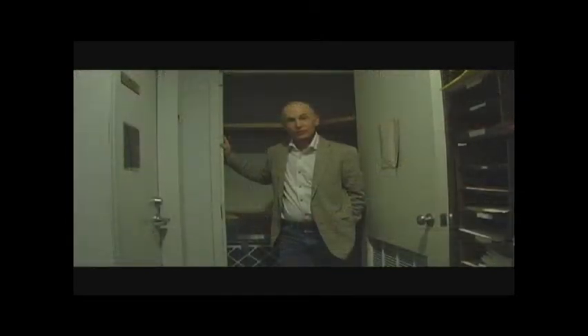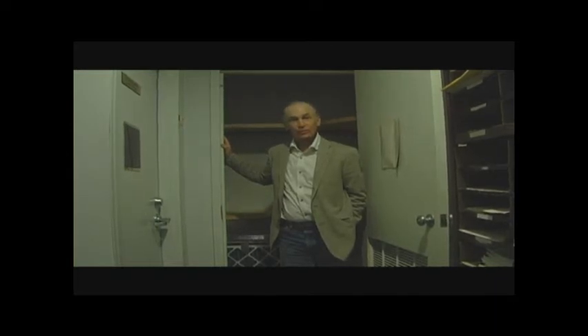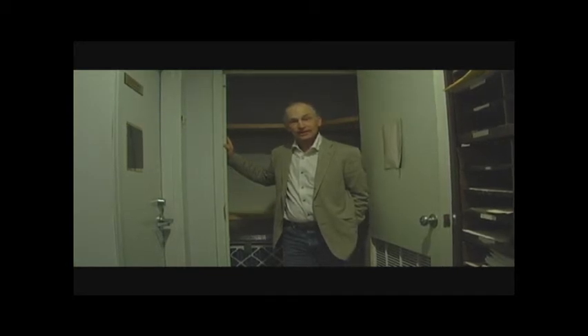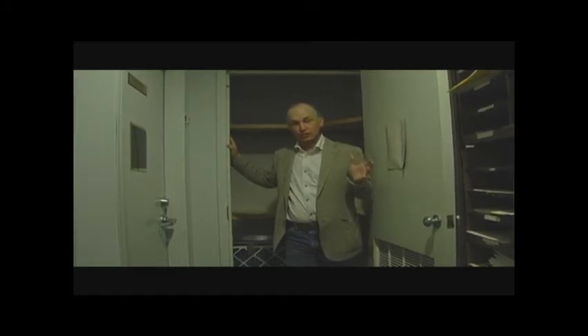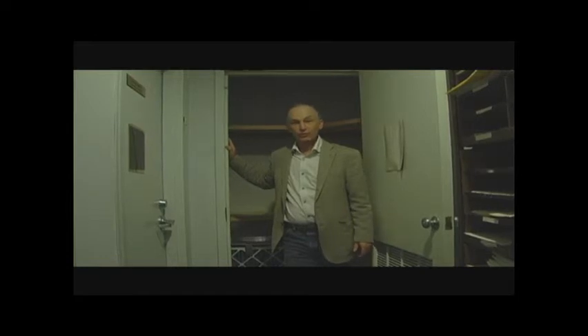I'm Dan Crowe, your Eco-Inspector, and we're going to go over some building science here from a practical point of view. We're in the office wing that was built in 1998. They've had all kinds of moisture problems related to this group of offices and hallway. The reason was we had supply air going out, feeding the rooms, but an inadequate return air pathway.